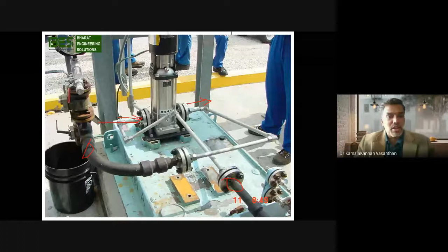So we need to ensure that these pipelines are also given much care at each and every point of installation. The basic thing we say is use an eccentric reducer, not concentric, as air pockets will build up at these places. And if it is suction from below the pump, it can be taken up in this way.